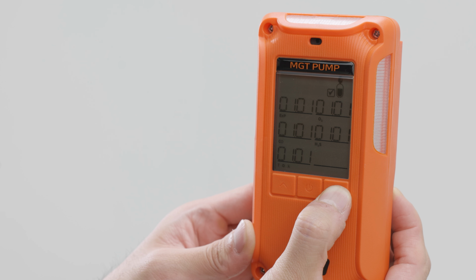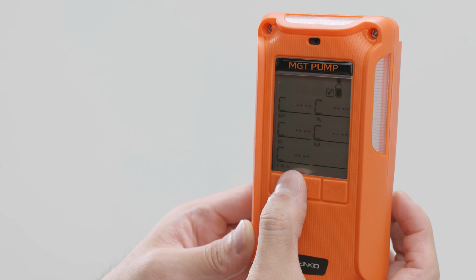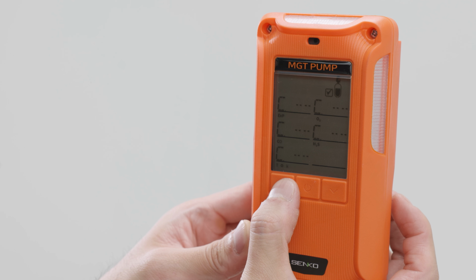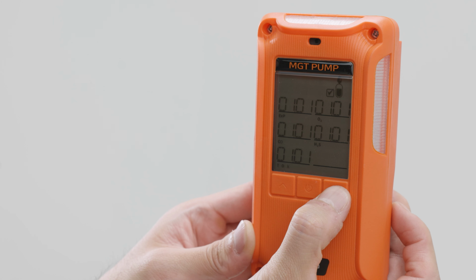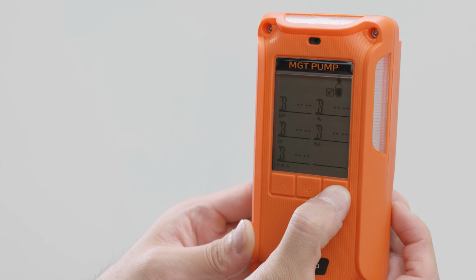Finally, the calibration information screen appears, showing the calibration gas type, date and time, the last calibration date, and the remaining days for the calibration and bump test intervals. This helps users manage routine maintenance and testing schedules accurately. Before performing calibration, always verify the calibration gas information to ensure correct and reliable operation.